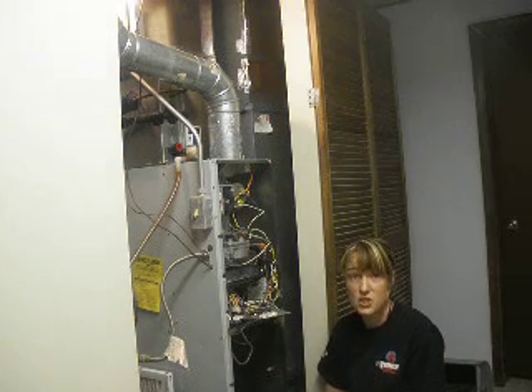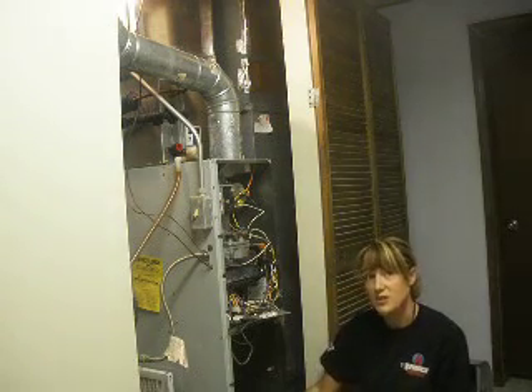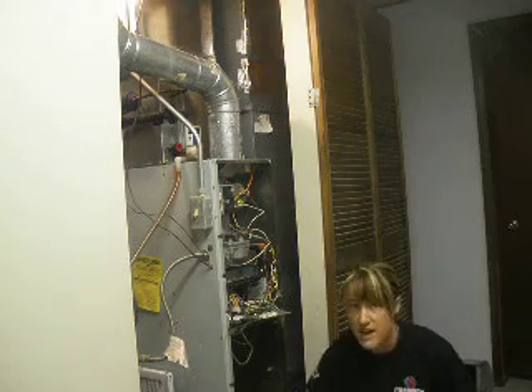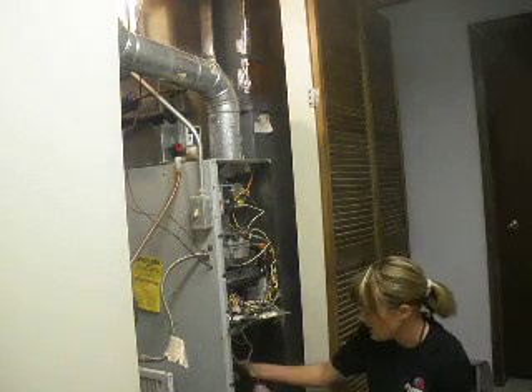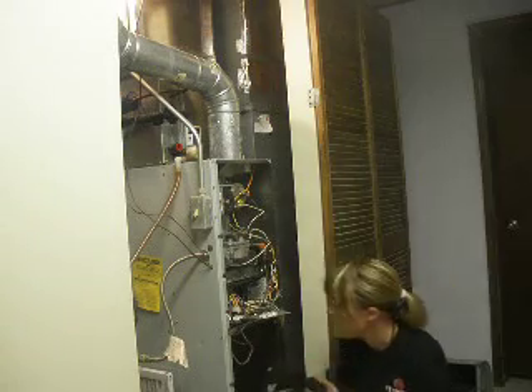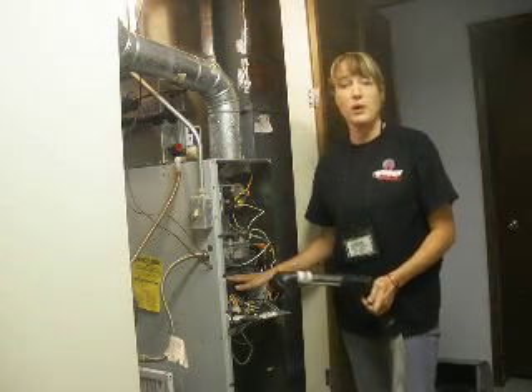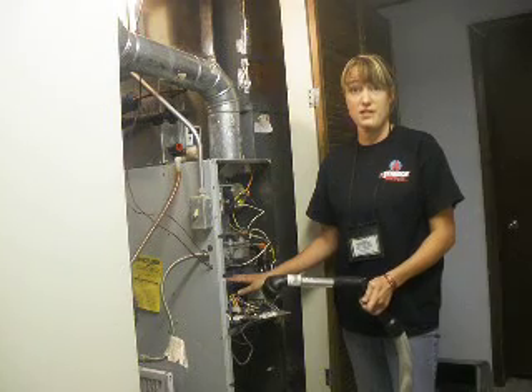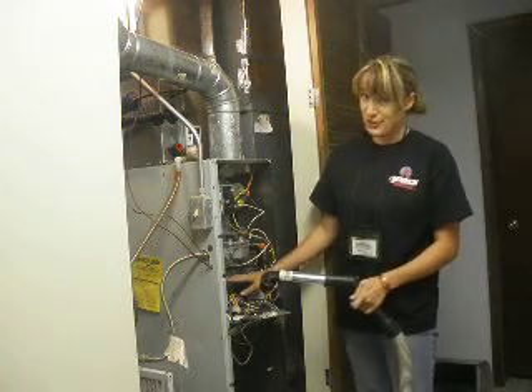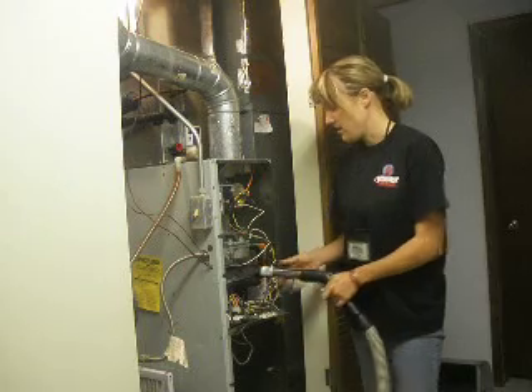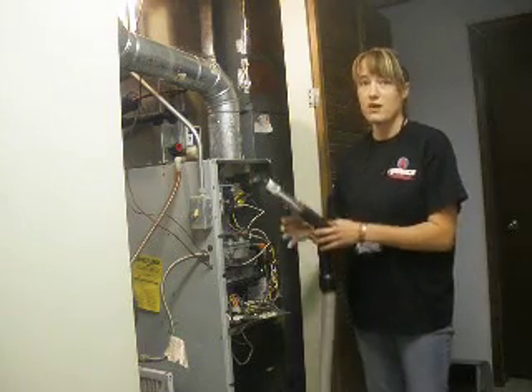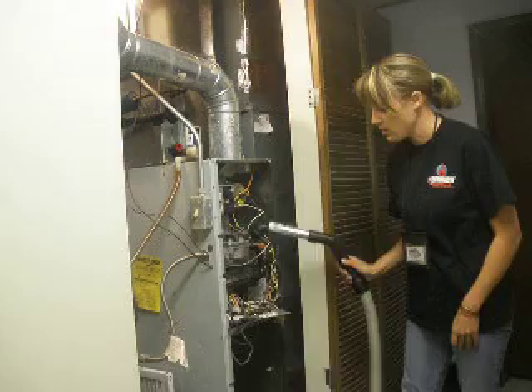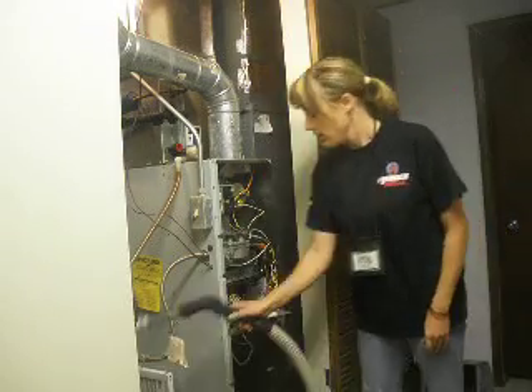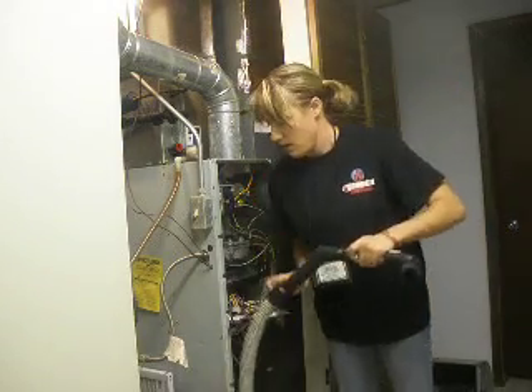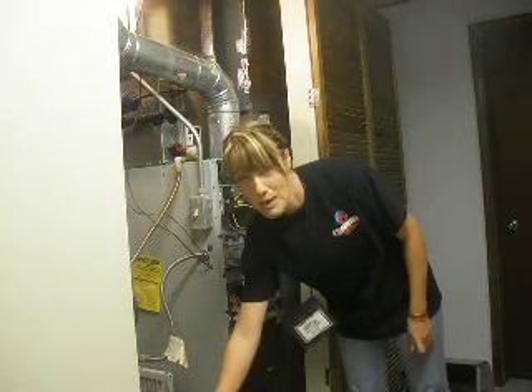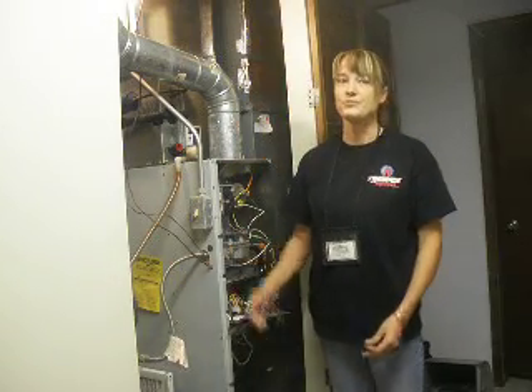If I find the heat exchanger to be in good working order, I continue to clean the furnace, vacuuming the entire return air area. And then I will use a blast of CO2, or when I'm performing the duct cleaning, I will have my compressed air, environmentally friendly compressed air, to clean this entire area while I'm vacuuming. I'll vacuum inside the entire compartment, around the area, and once that's completed, I will reassemble the furnace and run it through another heat cycle.